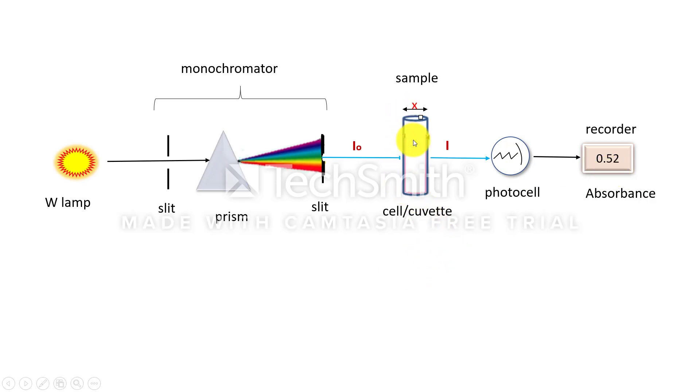Coming to the working of spectrophotometer, first the cuvette is filled with blank or reference solution. If you want to measure the absorbance of the colored substance, the solution is made in water, then the water will be a reference or blank solution. So first blank solution is filled in cuvette and the monochromatic radiation is allowed to pass through it.